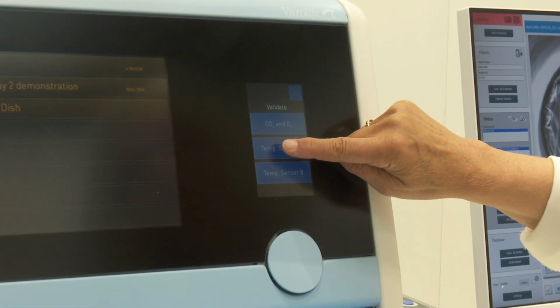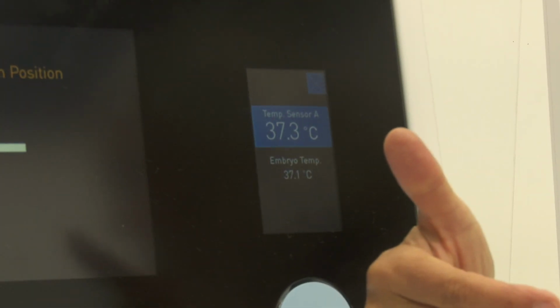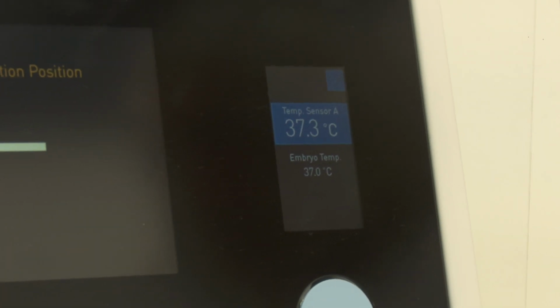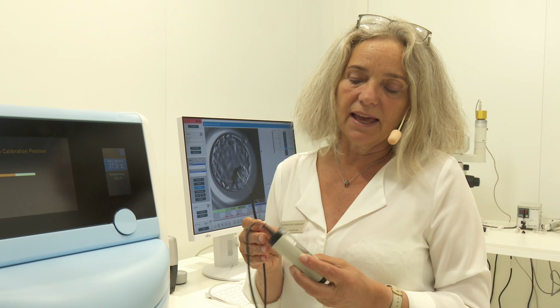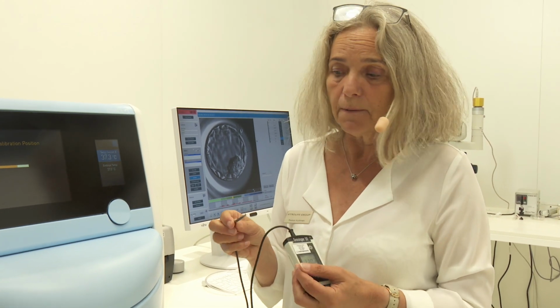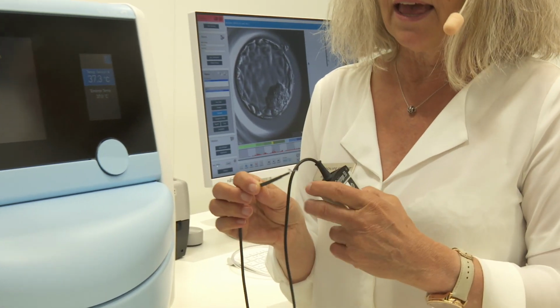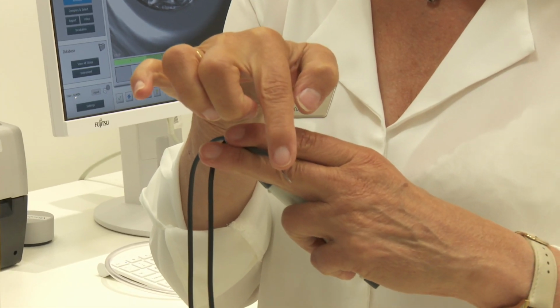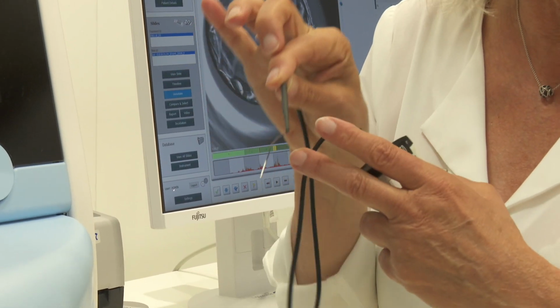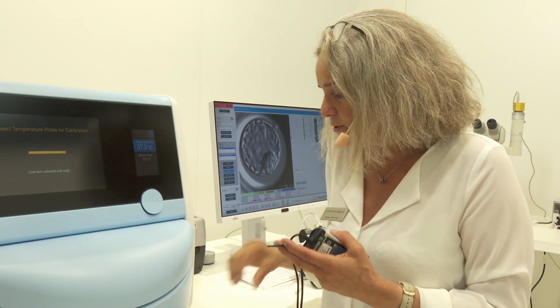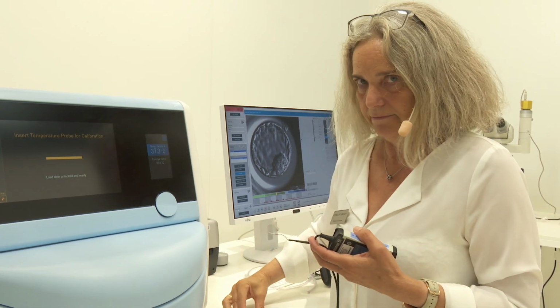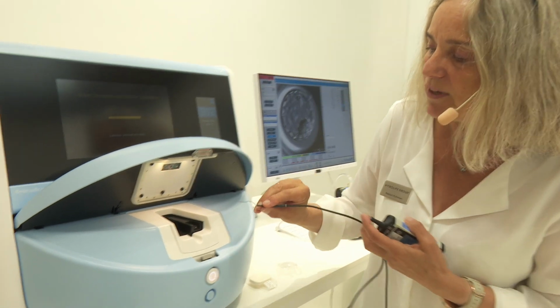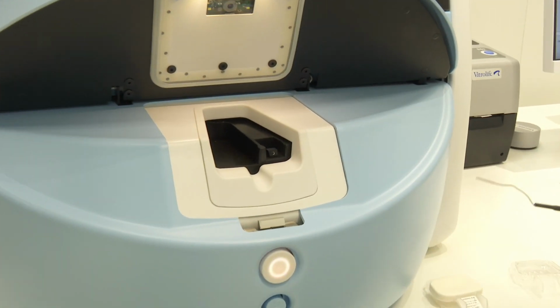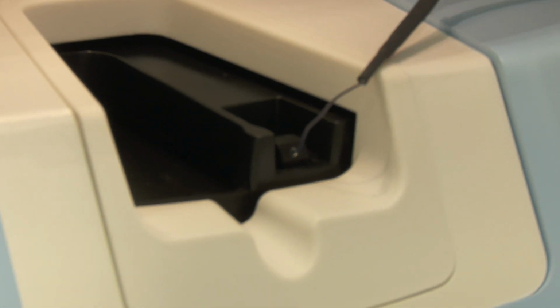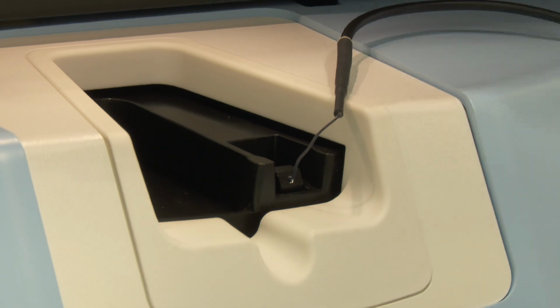So we take first the temperature sensor A, and it will move to this area where I'll put in the probe. What we recommend is a high precision thermometer. And what is very important is that the probe we use has a diameter of 1 millimeter, because it has to fit directly into this hole and go into a channel where it gets very close to where the embryos reside. So now it moves to this area, and I need to have my glasses on, sorry, because it's small. So you put the probe into the channel here, and make sure it remains inside while you do your measurement. So you can take the cable up here and just close it.